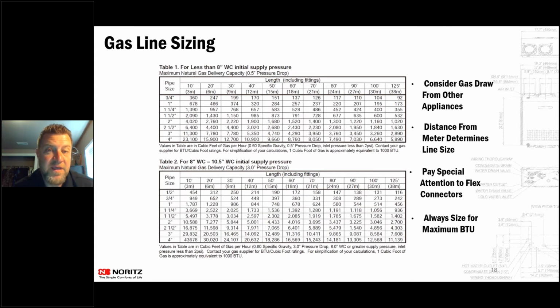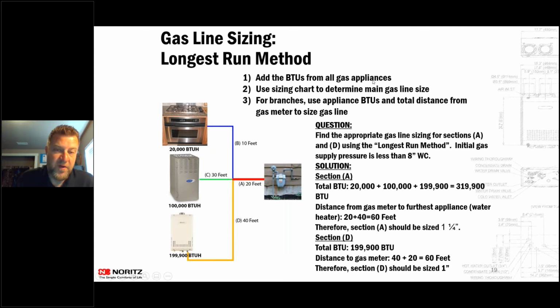Some houses have enough gas coming in, but a lot of houses that are out there, you're going to need to upsize that gas line coming in. One thing I've seen a lot of people do is they'll actually just run a gas line straight off of the meter directly into the tankless water heater, so they don't have to upsize the whole system. If it has enough CFM through that meter, you don't need to count that as your whole home run. But for that gas sizing, you want to add up all the BTUs from all the gas appliances that are in the house, using the sizing chart and your derating that you're using to find what that total BTU really needs to be.